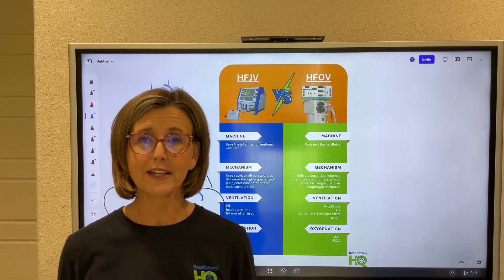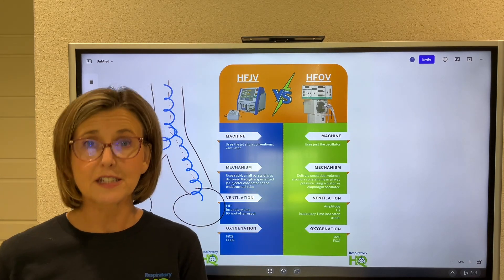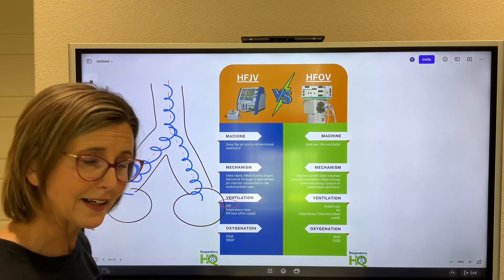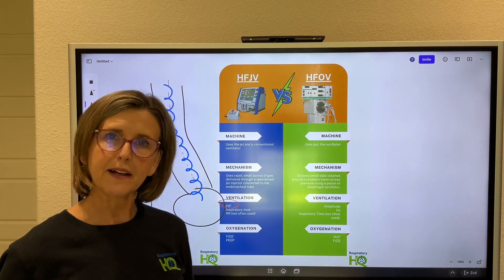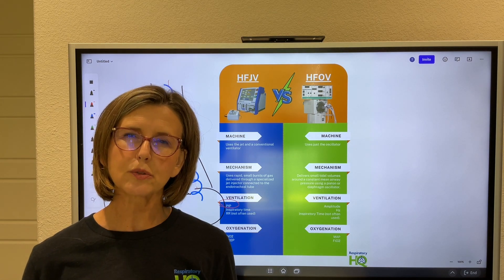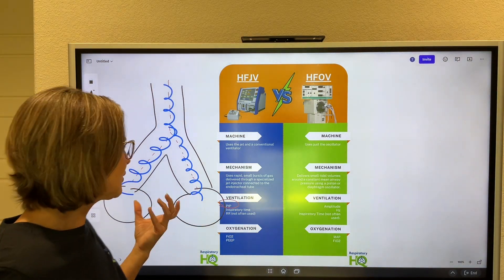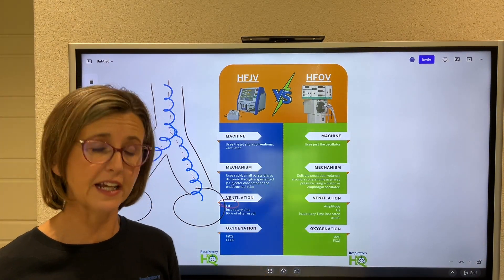When we need to change ventilation on the jet, the primary way is to increase the PIP on the jet ventilator. Increasing PIP increases tidal volume and blows off CO2 — that's the primary way to ventilate. You can also use I-time; a longer I-time allows more time for gas exchange and moves a bit more tidal volume. However, increasing I-time decreases E-time, so you must be very careful about air trapping. Respiratory rate can be used but is not commonly adjusted. PIP is the primary way to adjust CO2 removal.